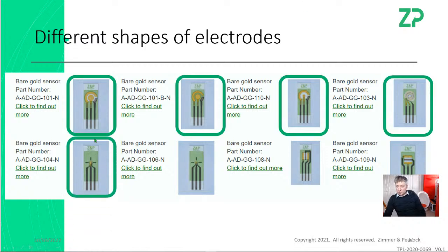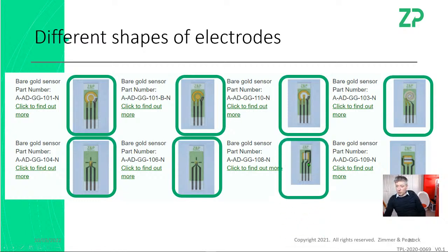Here we have a very much smaller electrode. Our idea here was that people might want to make wearable or implantable sensors and would want to test out those sensors or those sizes. This one's even smaller. Now this electrode was based like this because earlier on I was talking about an in vitro diagnostic where a sample might come in and onto a sensor due to capillaries or microfluidics, and so we imagined that the sample might come in from the side, and so we had a sensor where the sample comes into the side and sequentially covers the electrodes.